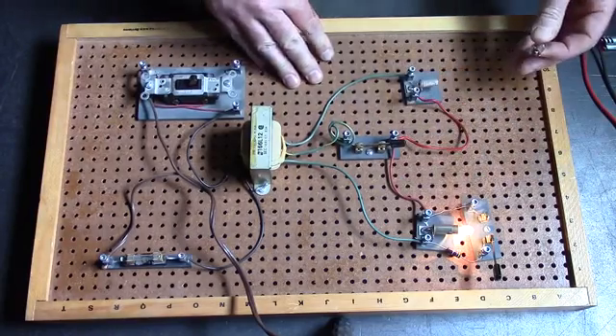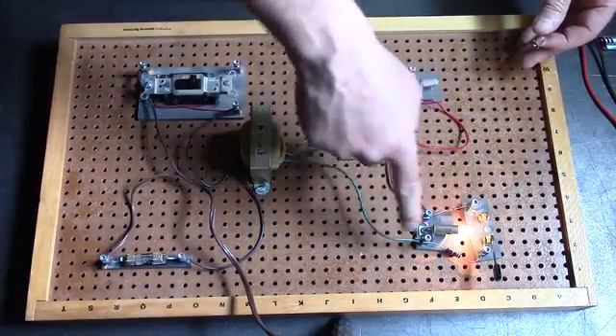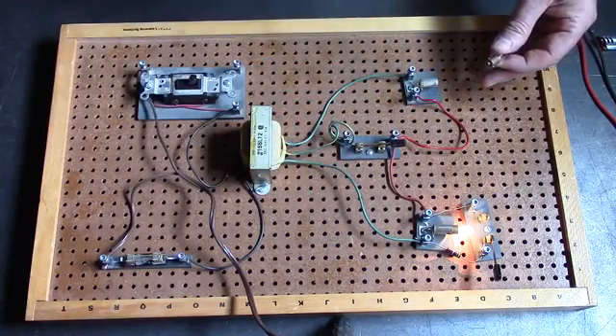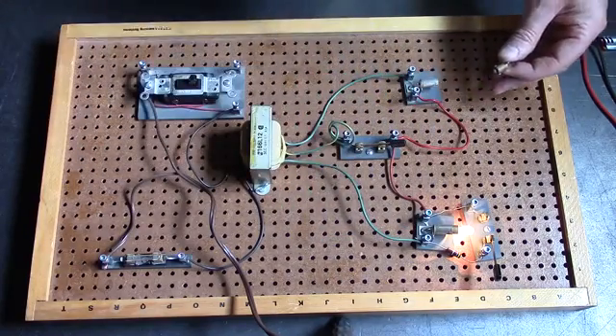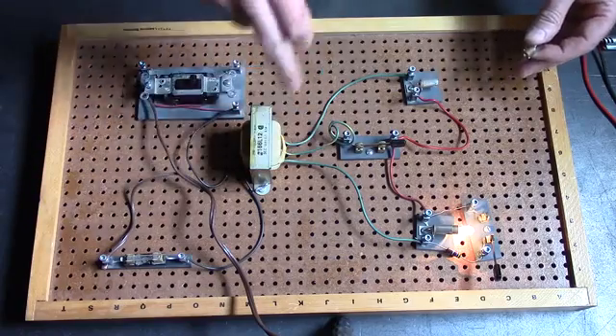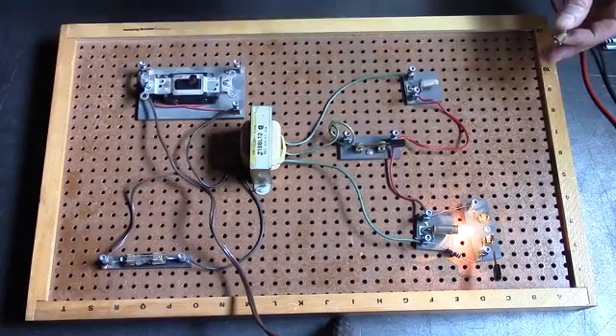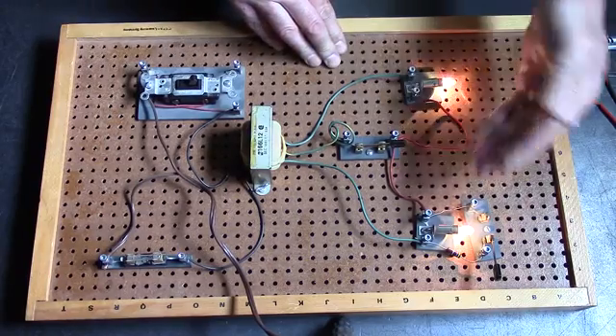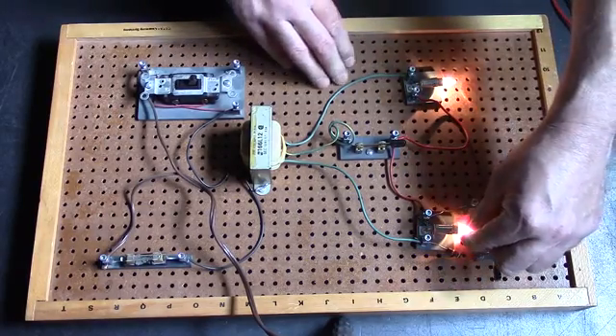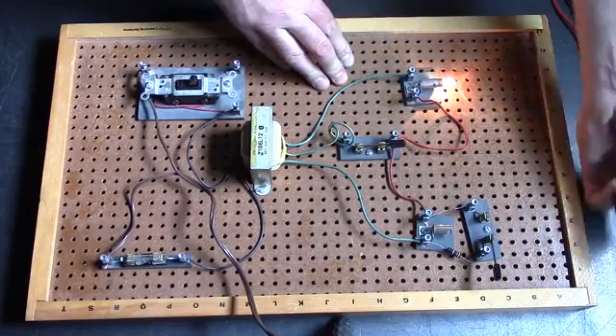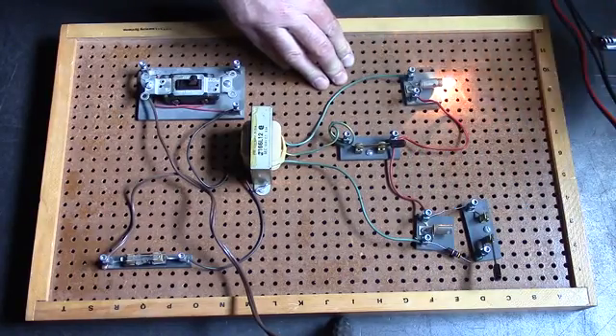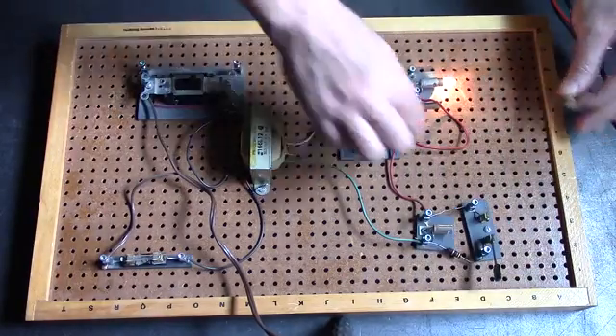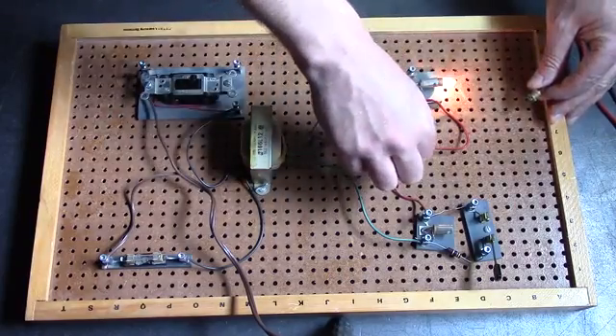The other lamp can still function. It's basically functioning on a half voltage supply from one side of the neutral to the end leg of the secondary so we're basically using half of the secondary windings to power that lamp. Again put this lamp back in, this lamp's unaffected by whether or not that other lamp is present and of course if I take the other lamp out this lamp is fine with that as long as that neutral connection is present.